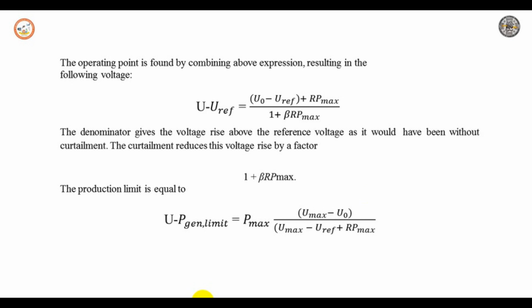So for example, during the course of a day with no generation, the voltage U naught moves up and down. The voltage with distributed generation is curtailed whenever it rises above U reference. So the maximum voltage U max will not be exceeded as long as it is not exceeded by the no-generation voltage. The resulting voltage variations are shown in the previous graphs we have seen. The comparison shows that curtailment instead of tripping significantly increases the amount of energy produced. The maximum voltage is never reached in this case because the no-generation voltage remains below the overvoltage limit.